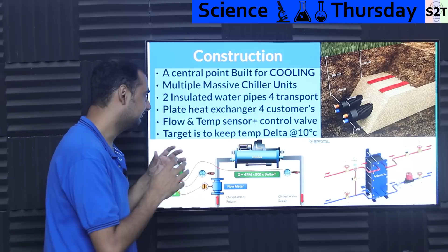It's just you have a building that is built for chilling. You have pipes which are insulated pipes. You have input and output, and then you have plate heat exchangers, and then you have a measurement unit which is just temperature sensors and a flow sensor. Nothing magical or complicated, and a control valve that does the actual control. And then you bill them based on how much energy they consumed.